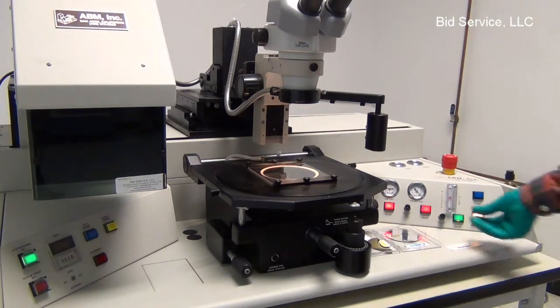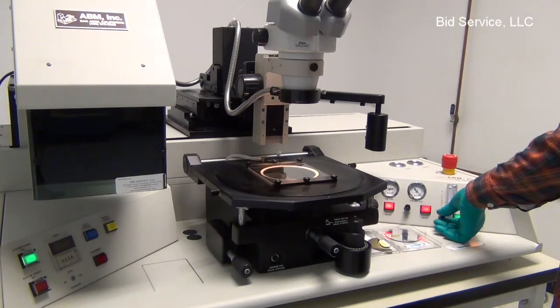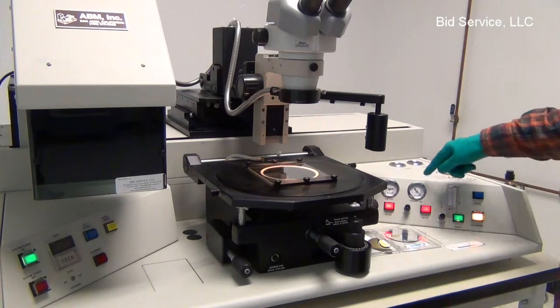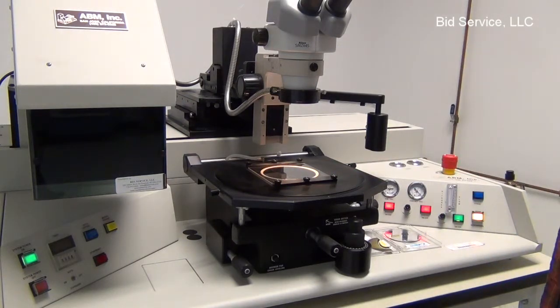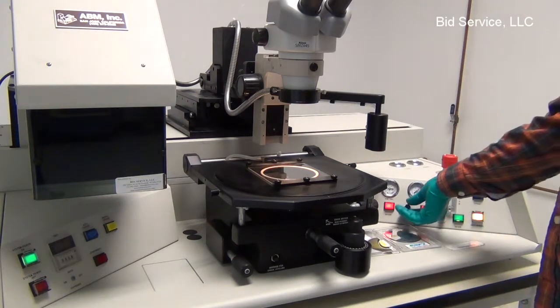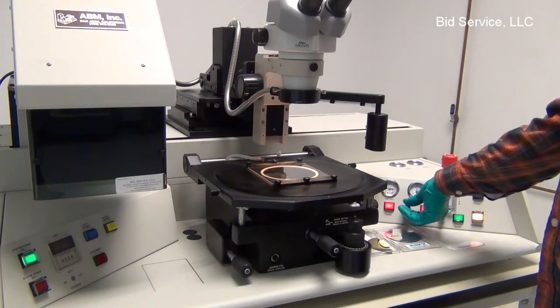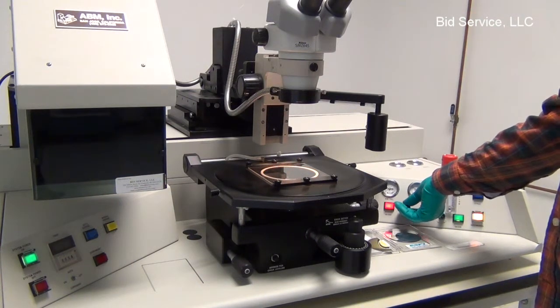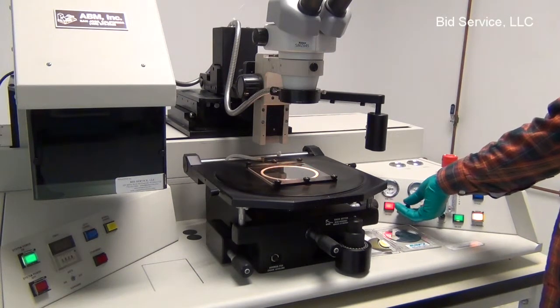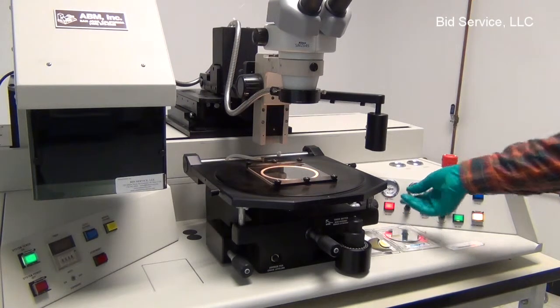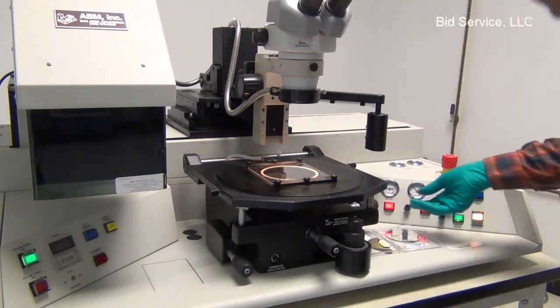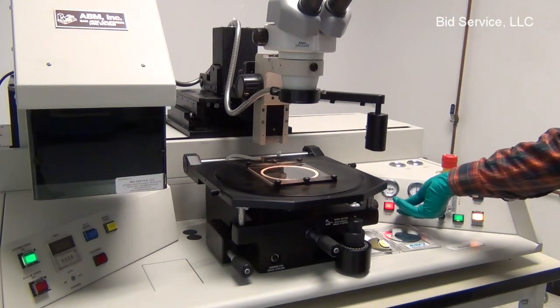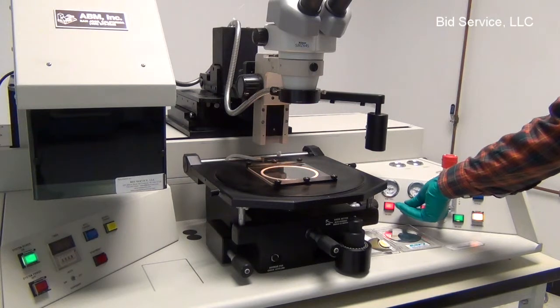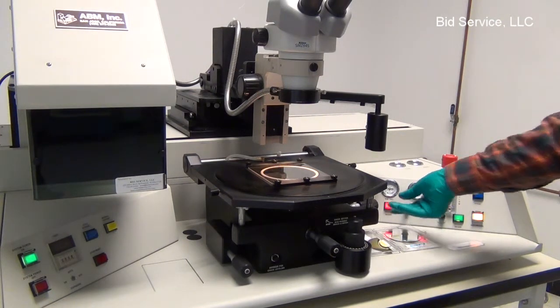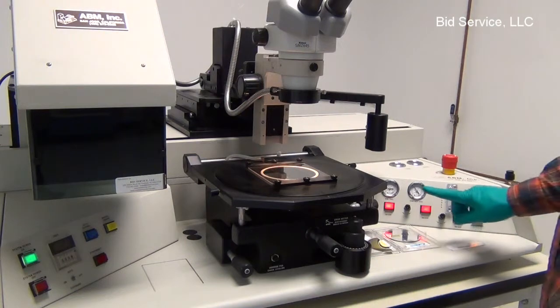Press the contact vacuum. There is a vacuum generated between the substrate and the mask. And there's an adjustment knob to adjust the contact vacuum level. You can select about 22 or 25 inches contact vacuum for hard contact, and about 15 inches mercury for soft contact, whatever is the desired value. Once you set the contact vacuum level, the unit is ready for exposure.